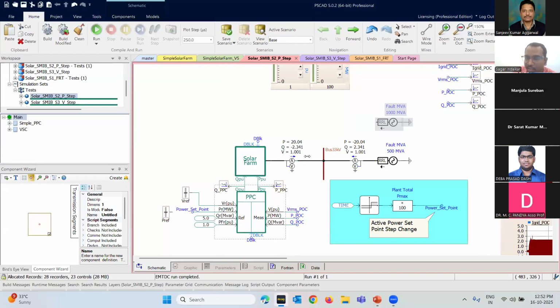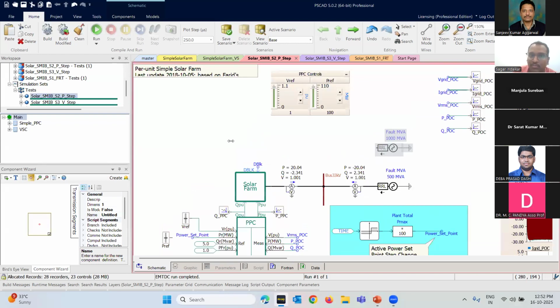On the right, typically what you have is a collector system. I have not modeled it here. Otherwise, there could have been a cable model present with the aggregated cable plant, and then your main power transformer would have been here. This is 33 kV, and this would have been at, let's say, 110 kV. This is a very simplified example just for demonstration purpose.